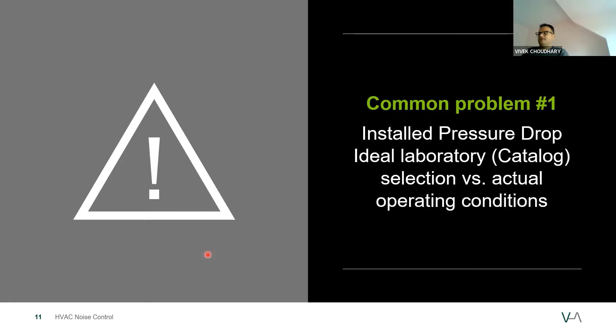When I say ideal or lab condition pressure drop, we follow the ASTM E477 testing requirements, which require leaving 5 diameters of straight duct at the silencer inlet and 10 diameters of straight duct at the silencer outlet. So for a 5-foot straight silencer, we're talking about 15 to 20 feet of straight duct. How many times do we have that much space in any building? Almost none, right?